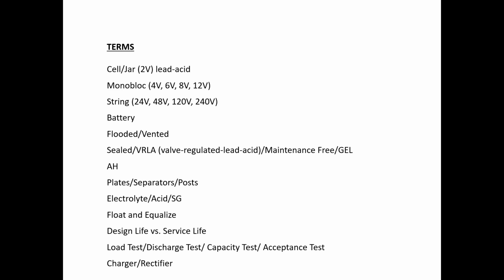And then charger, rectifier. Capacity test? Capacity test, correct. Capacity test, load test, acceptance test. Acceptance test obviously is done at installation to make sure what they sold you was actually delivered and installed as far as performance. But you can interchange all those terms, pretty much. The capacity test, load test, and discharge test are all the same thing. And then rectifier or charger, the DC plant.